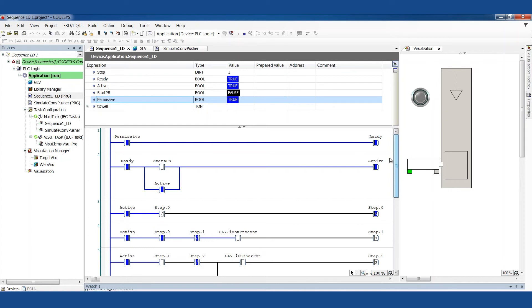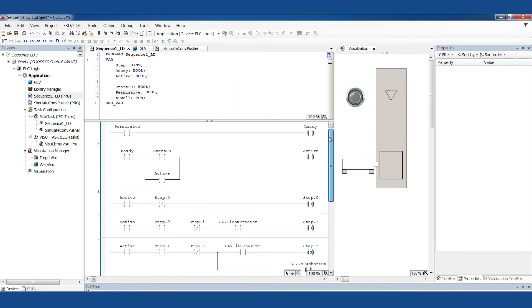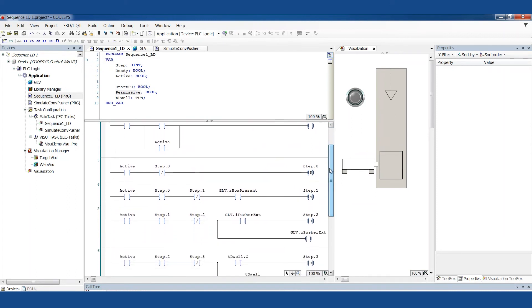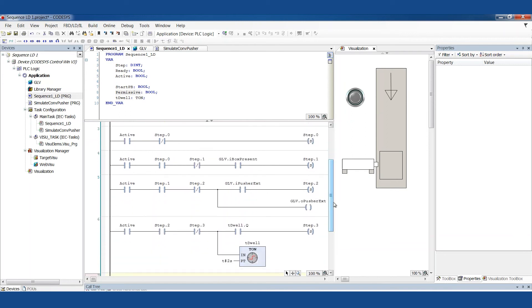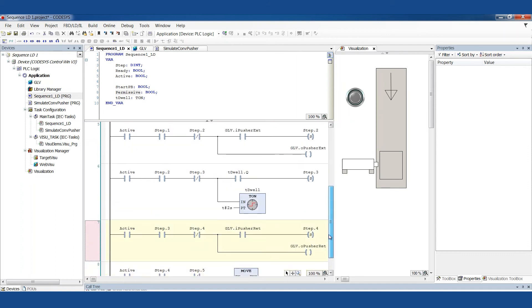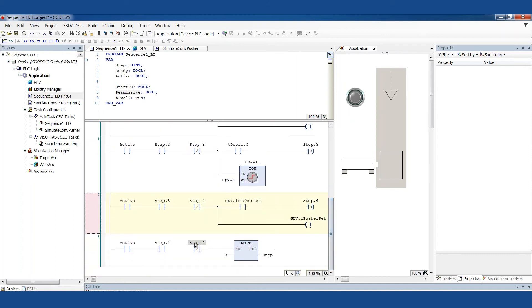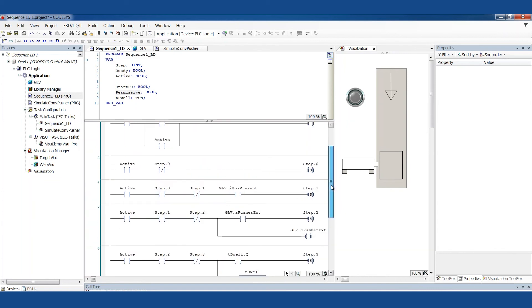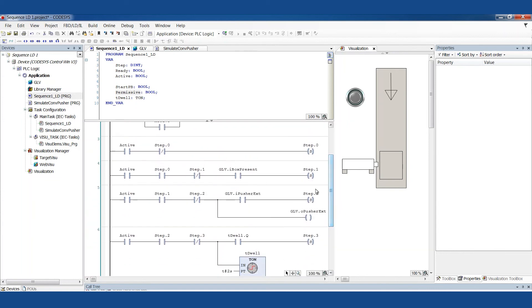The reasons I don't like it is that it's inflexible. So here I have step zero and step one and step two. What happens if I decide I need a step 1.5? There isn't really a good way to do that. I could just grab the next available bit number. In this case, bit five or maybe bit six. I don't have a step five or six right now. I could put that in there, but then the numbers don't line up. And personally, I think that would be confusing and frustrating to try and look at and debug.